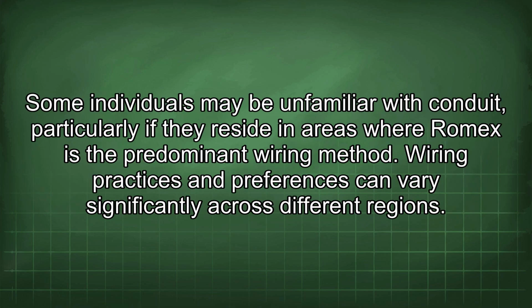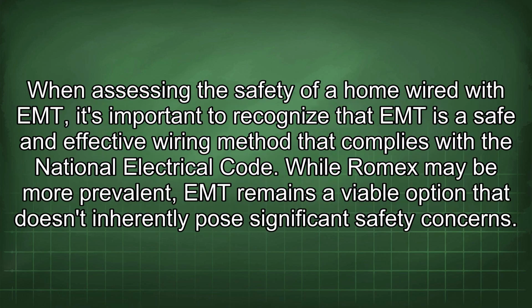Some individuals may be unfamiliar with conduit, particularly if they reside in areas where Romex is the predominant wiring method. Wiring practices and preferences can vary significantly across different regions. When assessing the safety of a home wired with EMT, it's important to recognize that EMT is a safe and effective wiring method that complies with the National Electrical Code. While Romex may be more prevalent, EMT remains a viable option that doesn't inherently pose significant safety concerns.